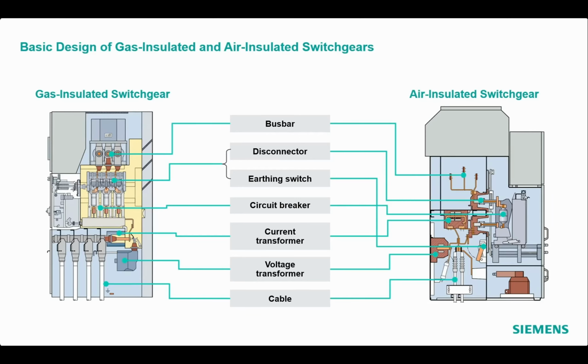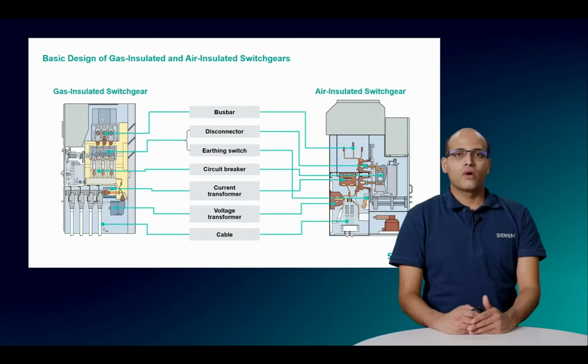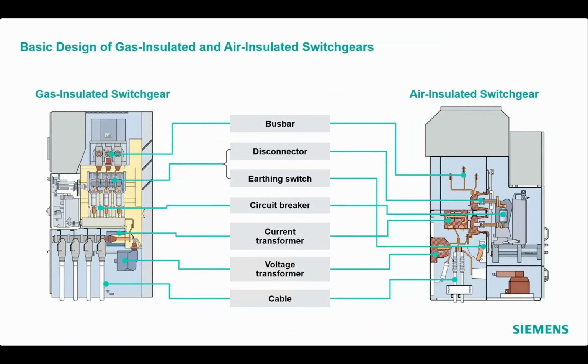Similarly, the voltage transformers, in short VTs or potential transformers, transform the high voltages into a lower level that can be used by protection relays or meters for protection and measurement purposes respectively. At the bottom part of the picture of gas-insulated and air-insulated switchgears, you can observe the cable connection compartment which helps in the termination of incoming and outgoing power cables.